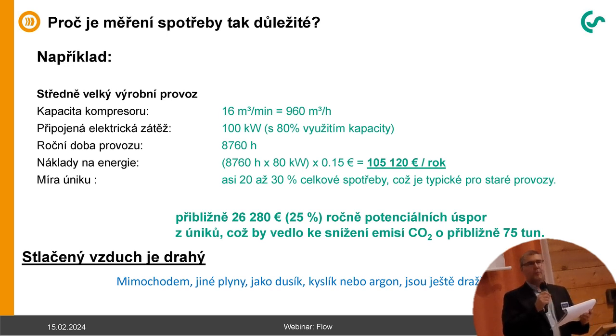So, about 20 to 30% of this compressed air will feed the leakages. All the compressed air systems are not tight, they have a lot of leakages, so the leakage rate is usually 20 to 30%. And this means even for a small factory, it's about 26,000 euro which could be saved if you take care of the leakage. So what we can say is that compressed air, it's only air, but it's a very, very, very expensive air. And not only compressed air, all the other things you generate from compressed air on site, for example, with a nitrogen generator you can have nitrogen, or with an oxygen generator you can make oxygen on site. And all the other gases are even more expensive than compressed air. So it's always worth it to find ways to be more effective.